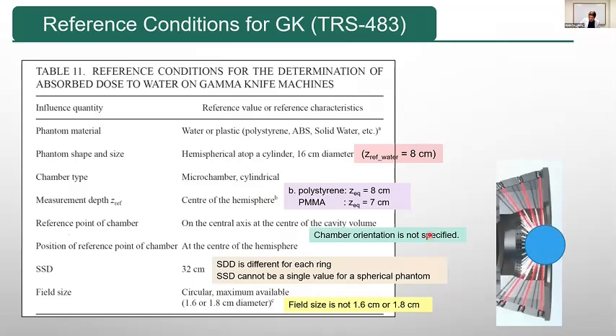Unfortunately, several minor things need to be corrected in the description of the GammaKnife reference field in TRS-483. Most of all, the source to surface distance cannot be a single value for a spherical phantom. The sources are on the surface of a cone, and the phantom surface is a sphere, so we cannot define a single value. And the field size is not 1.6 or 1.8 centimeter for the type C model. It's just that 16 or 18 is the name of the collimator. The field size defined as the full width at half maximum is slightly larger than their names. Anyway, it is not important.